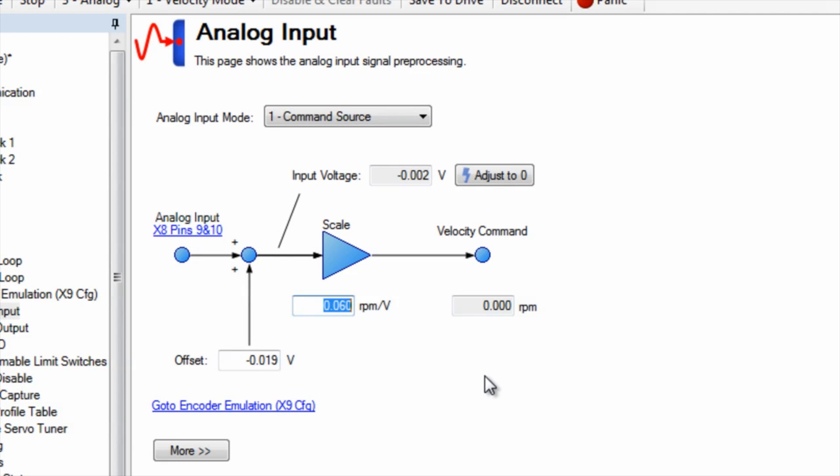For our motor with a speed of 3,000 rpms we will set the scaling to 300 rpms per volt. An offset can be created in one direction or the other. If a constant velocity is required with no input the offset can create this motion.